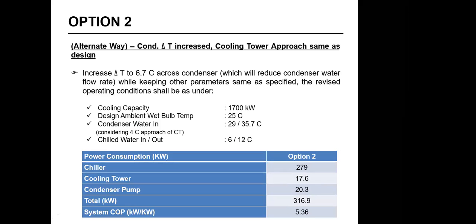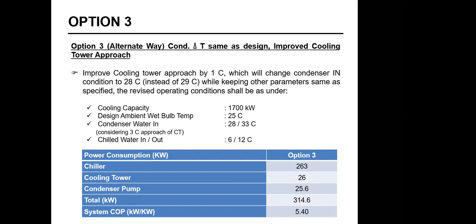So how can that be done? This is one option. If we have to optimize it, my basic design requirement remains the same, meaning he still needs 1700 kilowatt of cooling capacity for the building. Design ambient remains the same, 25. But I increase the delta T across my cooling tower. This is the one parameter I'm varying. Because of this parameter, my chiller power consumption has changed slightly, cooling tower performance has also changed, and pump power has also changed. Overall, my power consumption has reduced slightly, and my system COP has also improved a little bit. In this situation, what we have done is just increase the delta T of water flow across the condenser.